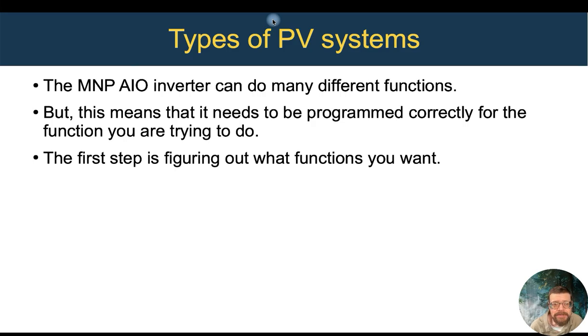We'll be working on a series of trainings on how to do those exact settings, and we're making some changes to our app to make it easier, where you can pick the system type and it gives you just the settings you need to modify for that system type. There are over 140 settings to program for this inverter, but usually between 3 or 4 and maybe a dozen at most are the ones you actually have to modify for a particular system type. The vast majority of those programming functions are left at the default values, but knowing which ones to change is the important part. This is the first video in a series of trainings on that. Over the next week or two, we'll be coming out with a bunch of additional materials for this.